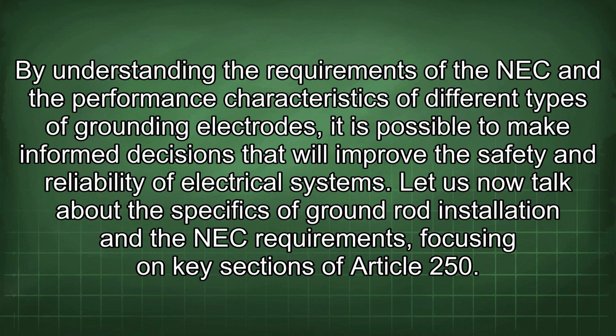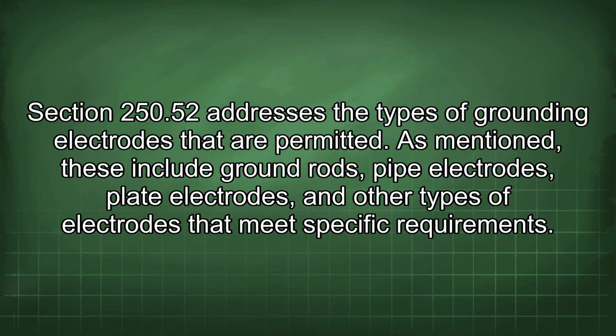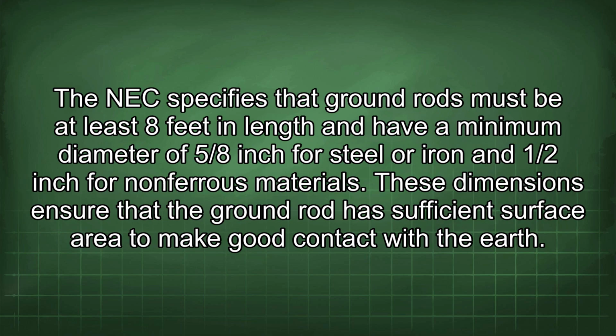Let us now talk about the specifics of ground rod installation and the NEC requirements, focusing on key sections of Article 250. Section 250.52 addresses the types of grounding electrodes that are permitted. As mentioned, these include ground rods, pipe electrodes, plate electrodes, and other types of electrodes that meet specific requirements. The NEC specifies that ground rods must be at least 8 feet in length and have a minimum diameter of 5/8 inch for steel or iron and 1/2 inch for non-ferrous materials. These dimensions ensure that the ground rod has sufficient surface area to make good contact with the earth.